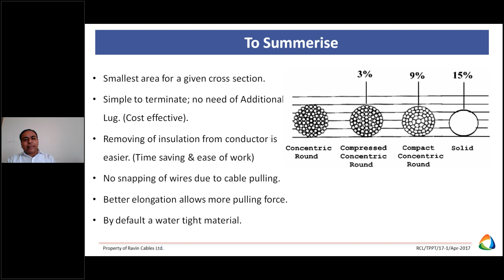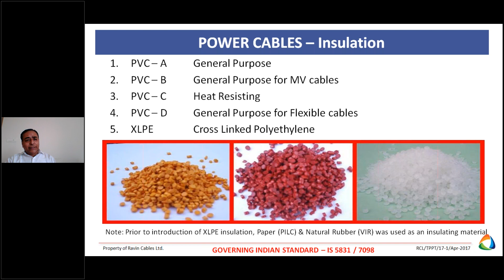This is the difference in how the diameters are different. In solid, the diameter is lesser as compared to concentric, then compressed and concentric round. Just for knowledge purposes, nothing more than that. Then we come to the insulation part. PVC is defined with various grades based on the continuous current rating and continuous temperature of the conductor. General purpose is normally used for 70-degree operation. Type B is also 70-degree operation. Type C is for 85 degrees centigrade, and XLPE is for 90-degree operation.